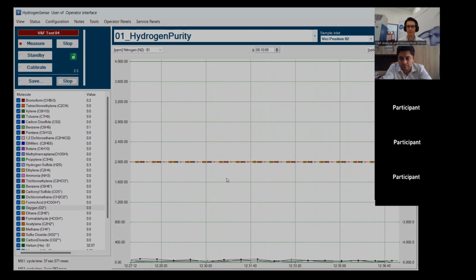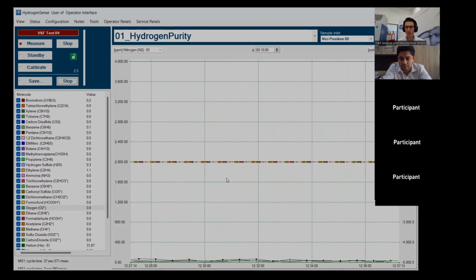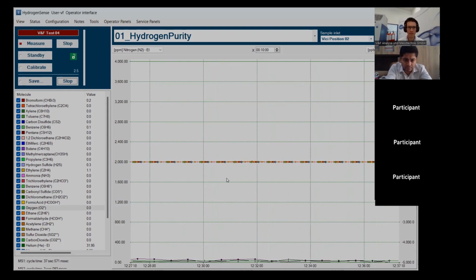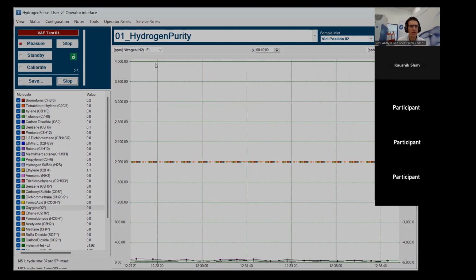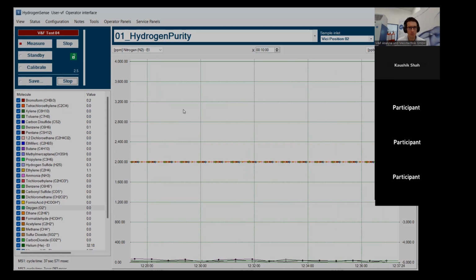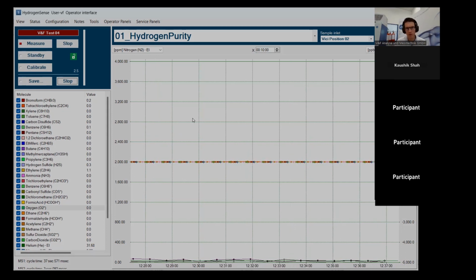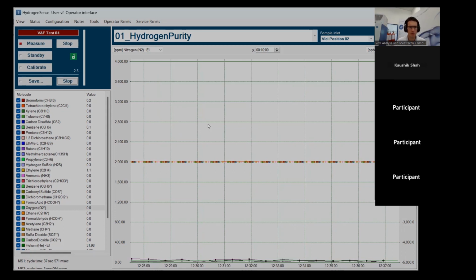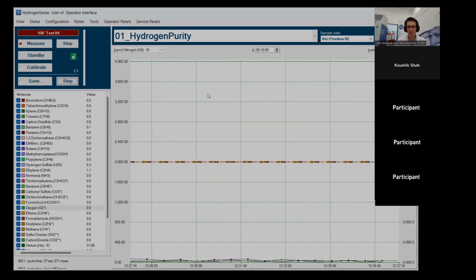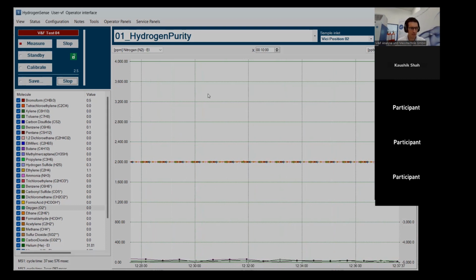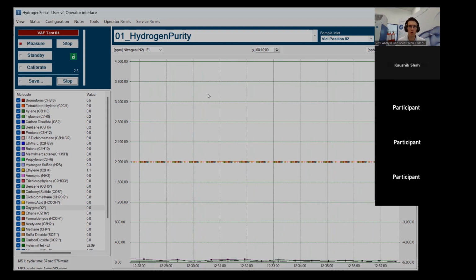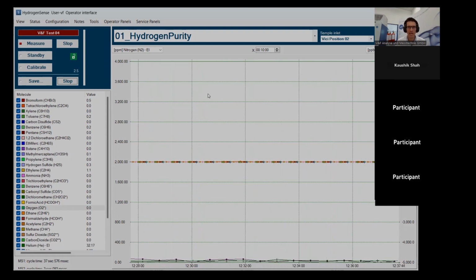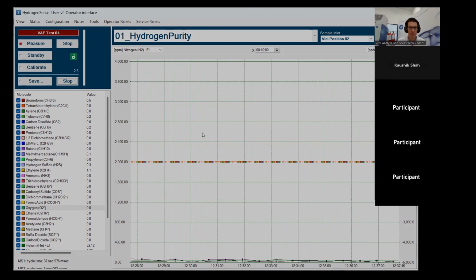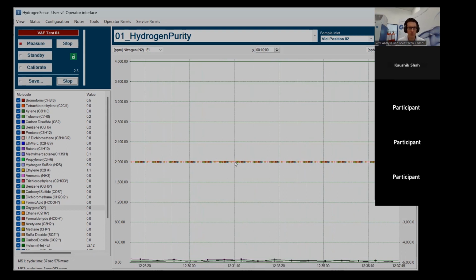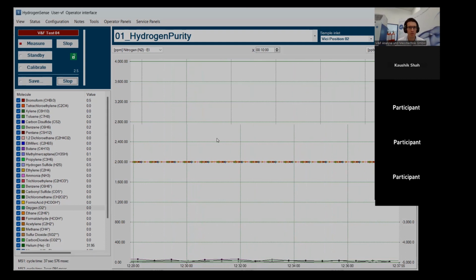How much minimum pressure is required for this sampling? Minimum pressure on the Valvebox inlet is a slight overpressure, I think half a bar. So it's 1.5 bar absolute or 0.5 bar gauge in order to operate the mass flow controller. The maximum is the bigger problem, because this multiplexer is only certified up to 5 bar gauge for hydrogen gas in order to be tight. So we usually recommend having pressure reduction beforehand and setting the pressure into the safe region of the multiplexer.